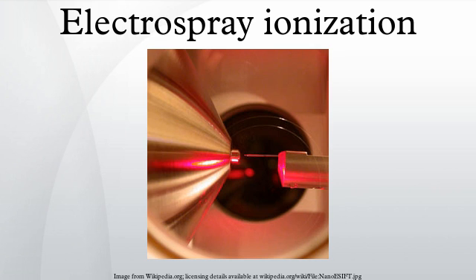Extractive electrospray ionization is a spray-type ambient ionization method that uses two merged sprays, one of which is generated by electrospray. Laser-based electrospray ambient ionization is a two-step process in which a pulsed laser is used to desorb or ablate material from a sample, and the plume of material interacts with an electrospray to create ions. The sample material is deposited on a target near the electrospray; the laser desorbs or ablates material from the sample, which is ejected into the electrospray to produce highly charged ions. Examples include electrospray laser desorption ionization, matrix-assisted laser desorption electrospray ionization, and laser ablation electrospray ionization.